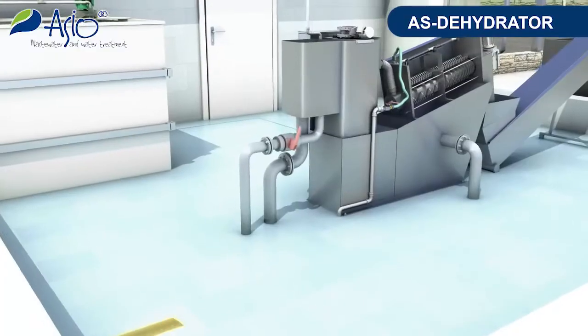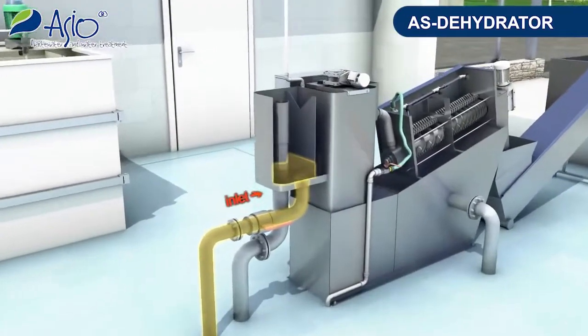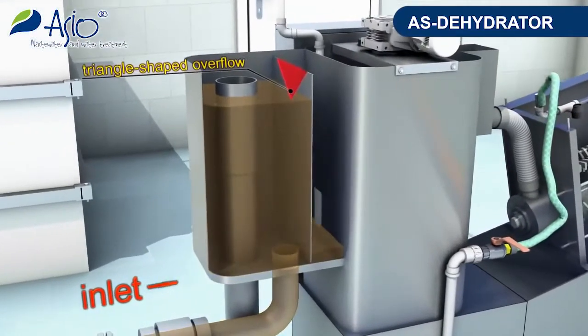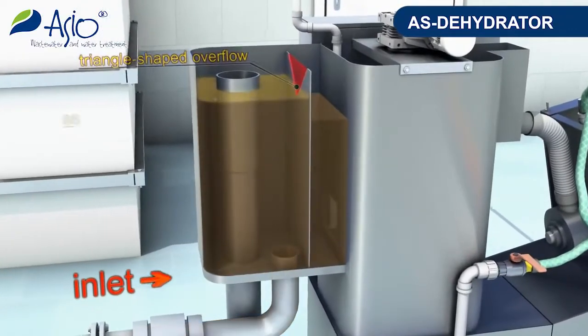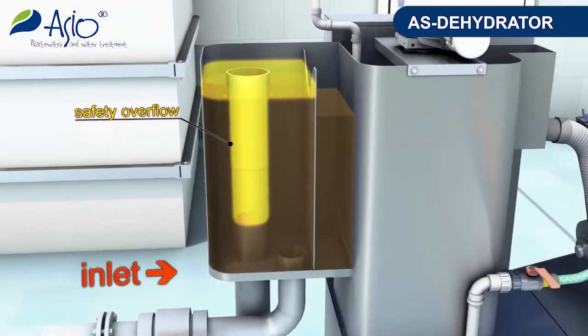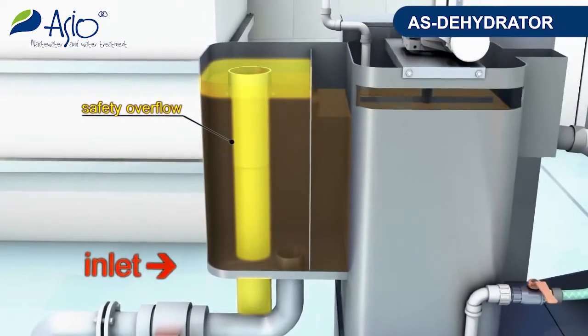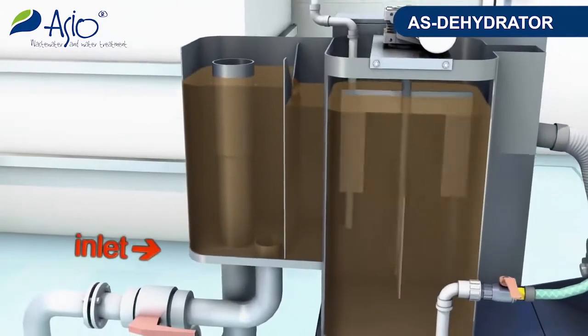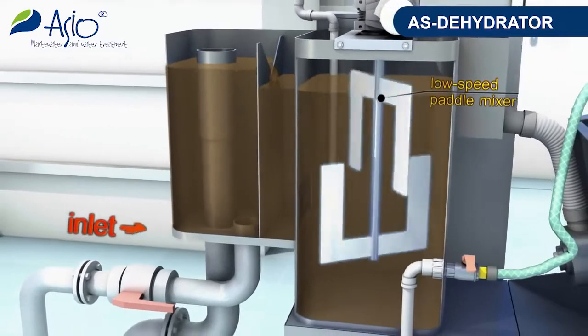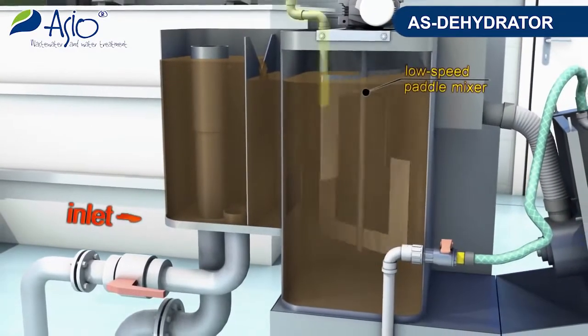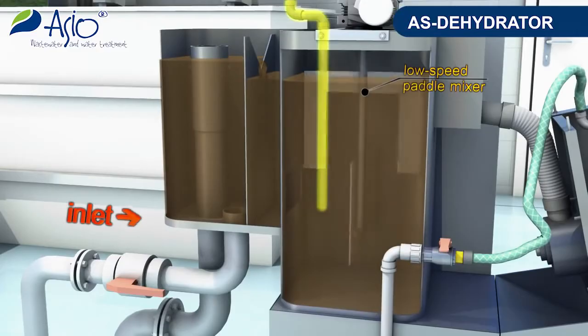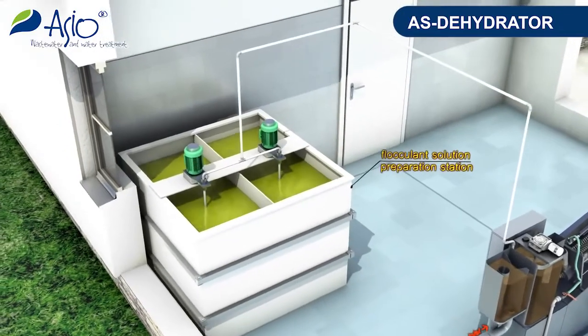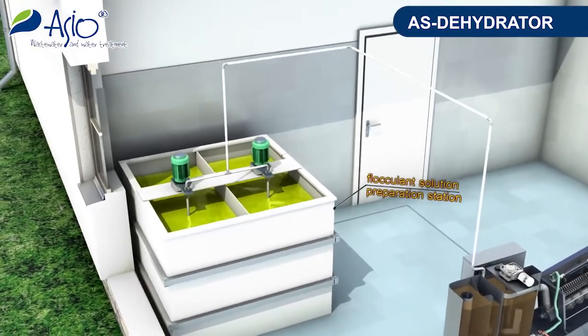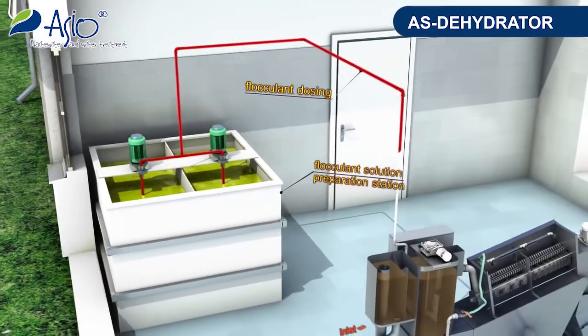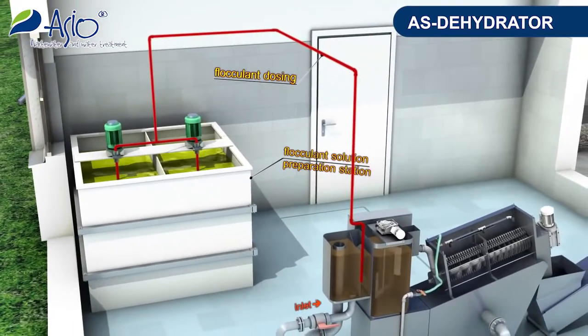Sludge is pumped into the dehydrator inlet tank, and from there it flows over a triangular overflow discharge into the flocculation tank. Sludge quantities exceeding the equipment capacity are returned through the safety overflow. The flocculation tank is stirred with a low-speed paddle mixer, and a polymeric flocculant is dosed into the incoming sludge. The flocculant solution is prepared directly at the wastewater treatment plant by mixing the concentrated reagent with water in an independent tank. It is then dosed in sufficient quantities by a dosing pump.